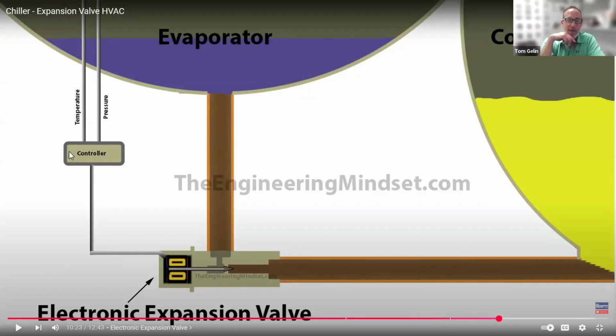of the valve. Yeah, I think the long and the short of it is that electronic expansion valve has a much more accurate control in that you're measuring the temperature and pressure of the refrigerant and controlling the pin to release a more precise amount of refrigerant from the condenser into the evaporator.